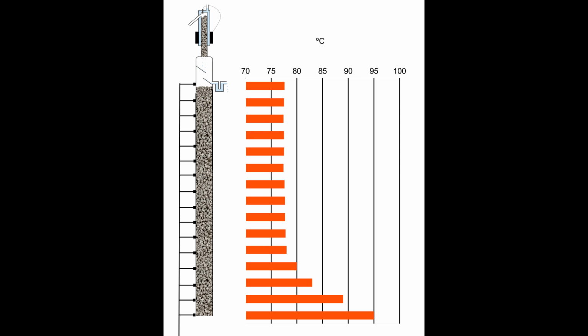It does not need to be measured with high precision because the corner at the bottom of the isothermal section has a large temperature rise from 78 degrees to over 90 degrees over 3 or 4 stages. The aim is to set up a festoon of temperature sensors along the surface of the column and to derive the control parameters from the length of this isothermal section. If the bottom of the isothermal section gets too hot, power is reduced.